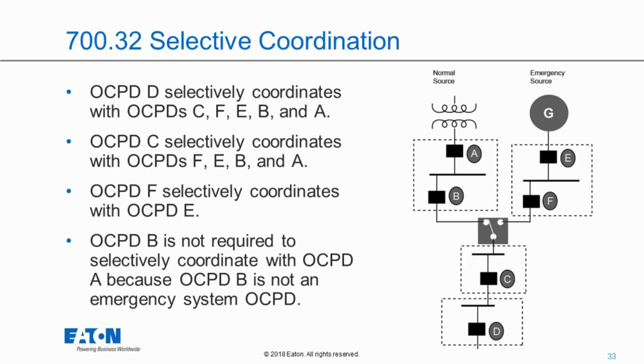However, if I go to the line side of the transfer switch on the normal side, if there's a fault on the load side of device B, it does not have to selectively coordinate with device A. Now, there are certainly benefits to having B selectively coordinate with A, but it's not required. The idea is if the fault occurs on the load side of B and the line side of the transfer switch, then it really doesn't make a difference whether B opens or A opens or both of them open, because at that point in time we're switching to emergency to go to the alternate source. So that's really the clarification of what is required and what's not required.